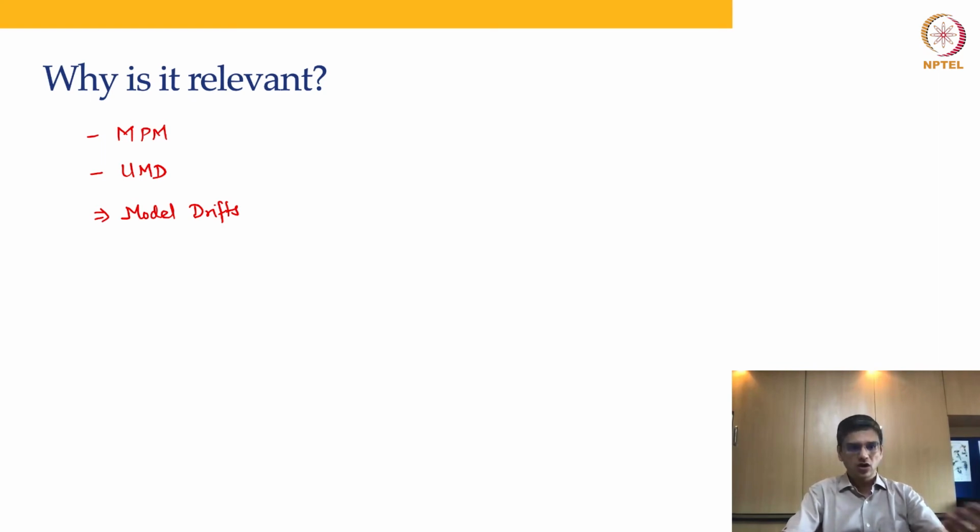So because of continuous use at high temperature, high pressure, and so on, the behavior of any equipment when it is new or newly serviced, and when it is say 5 months, 6 months, 8 months, 10 months into commissioning, is different. The model was built at time 0, so it was built with the perfect condition system in mind. But as time goes on, the system drifts, and that drift is sometimes not accurately captured in the model.